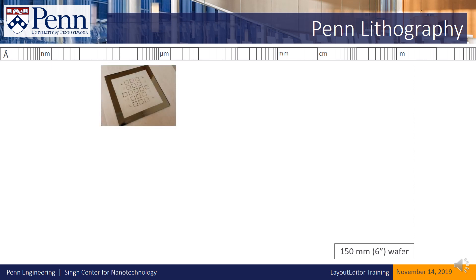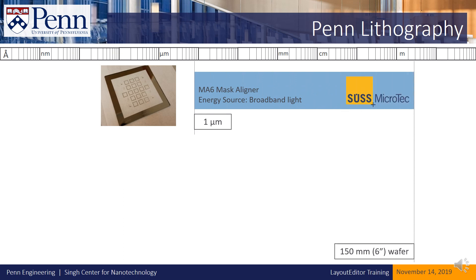First, we'd like to give you an idea of what you can do in QNF lithography. The lithography tools in the QNF can handle a variety of substrate sizes — any size up to 6-inch wafers, which includes 4-inch wafers and pieces. If you'd like to pattern features down to about a micron in minimum feature size, you should consider using the SUSS MA6 mask aligner. Exposures on this tool are usually fast, taking only a few seconds, but they are limited in minimum feature size compared to other tools.